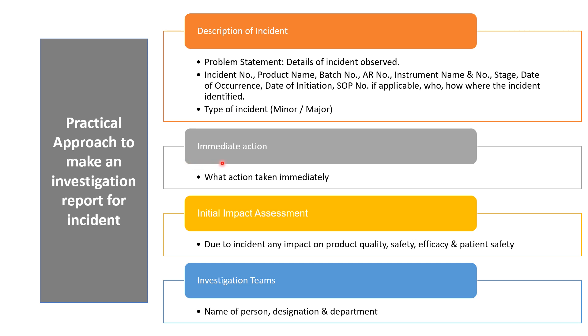The next section is immediate action — define what action was taken immediately after identifying the incident, such as placing the instrument on hold, initiating the incident, and performing a preliminary investigation. The next section is initial impact assessment — define the impact on product quality, product safety, and efficacy due to the incident. For example, if the sequence was interrupted before sample injection, there will be no impact on product quality.